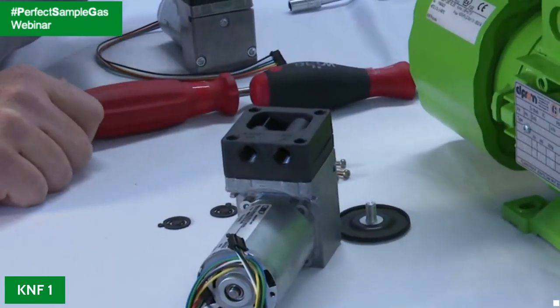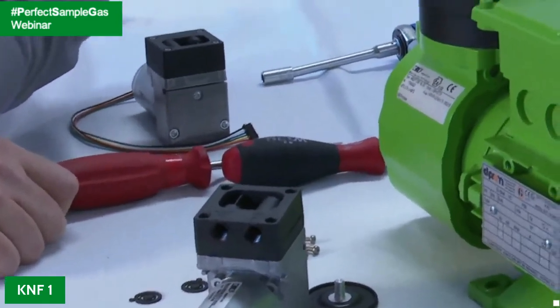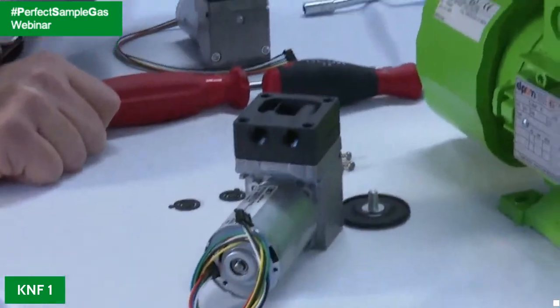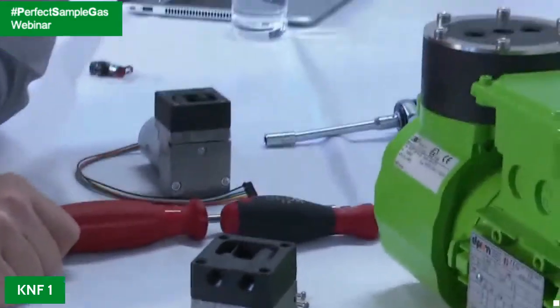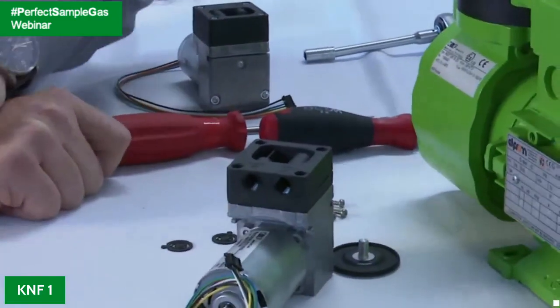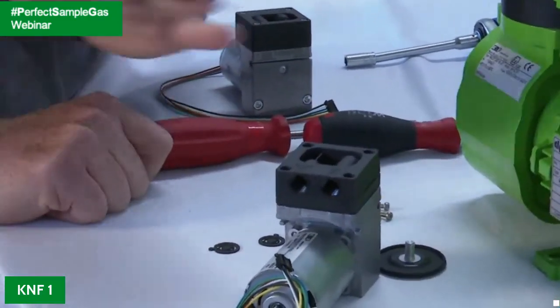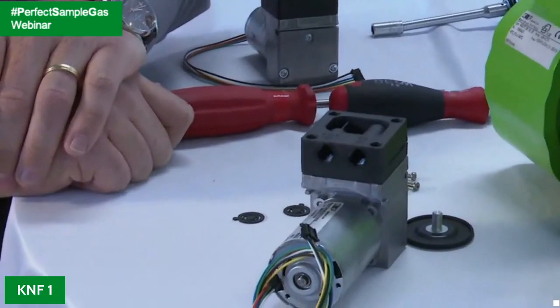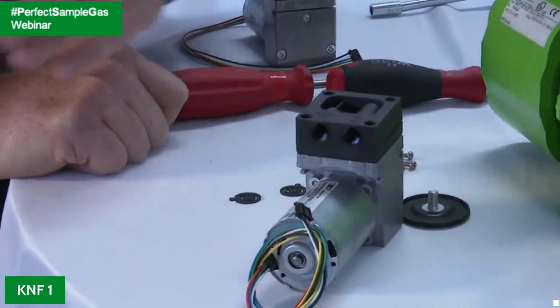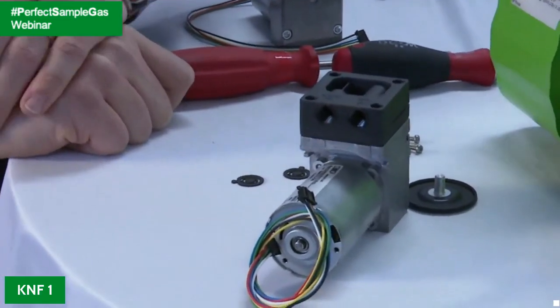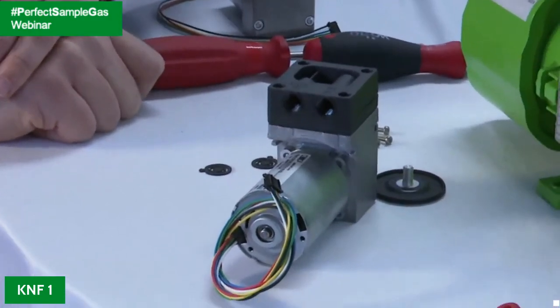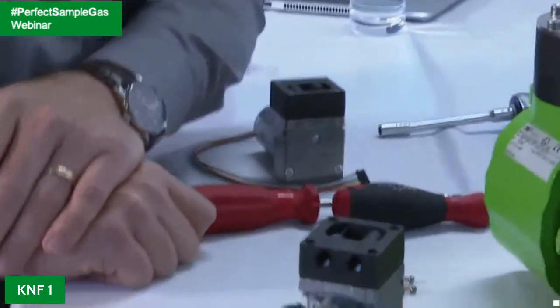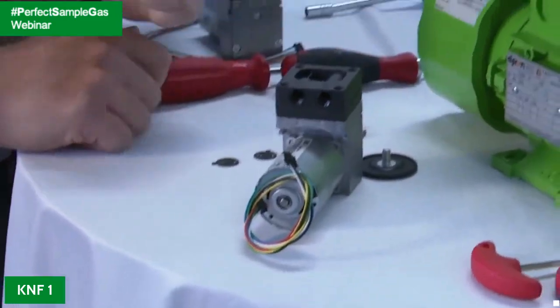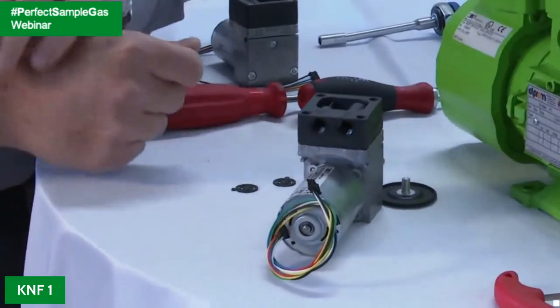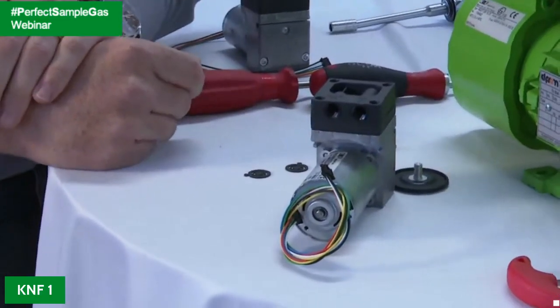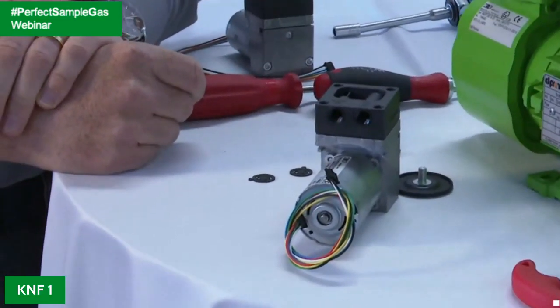And even though you mentioned, Felix, that there's a special technology to avoid mounting it the wrong way, that's specific to this particular pump. But the general behavior with a lot of other KNF pumps, or most KNF pumps, follows absolutely the same procedure. Sometimes you have to remove a few more screws, sometimes there's an additional sealing, or sometimes the diaphragm isn't in a closed service and is fixed with a screw. But the principle of servicing is similar for nearly every KNF pump.